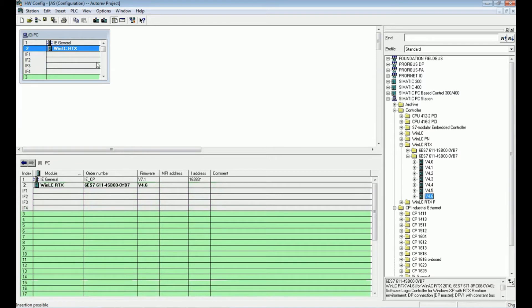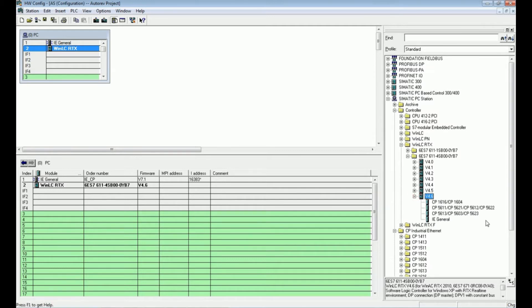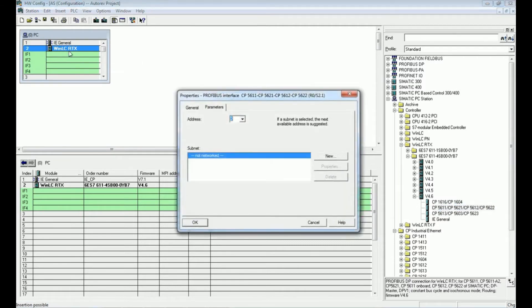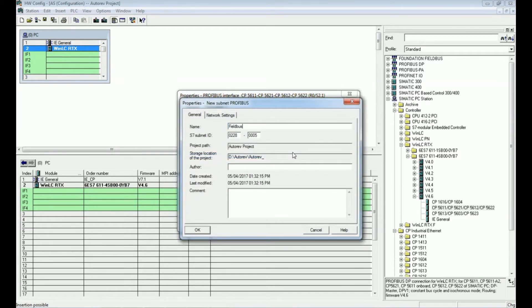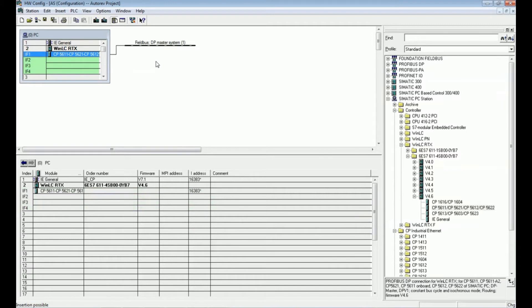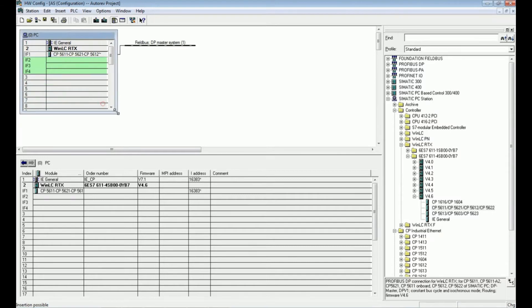After adding the RTX Box, we will add a communication processor to make communication between the automation station and the distributed I/O. This communication processor card is for Profibus DP. I am now adding this CP with the RTX Box. The system asks about Profibus addressing — I will keep address 2 and create a new subnet called 'Field Bus'. Field Bus will be the communication link between the automation station and the distributed I/O system. You can see the Profibus DP link is added in this station.